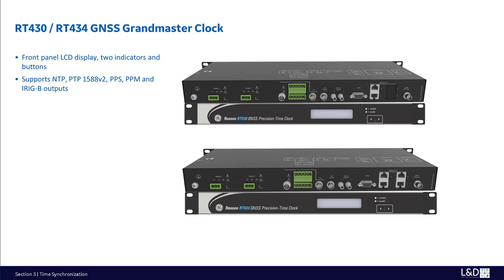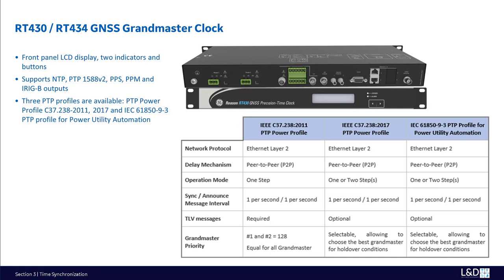Both clocks support NTP, PTP 1588 V2, PPS, PPM, and IRIG-B outputs. 3 PTP profiles are available: PTP power profile IEEE C37.238-2011 and 2017, and IEC 61850-9-3 PTP profile for power utility automation. IEEE C37.238-2017 and IEC 61850-9-3 are completely compatible and can work together without restriction on the same network by setting the domain number.